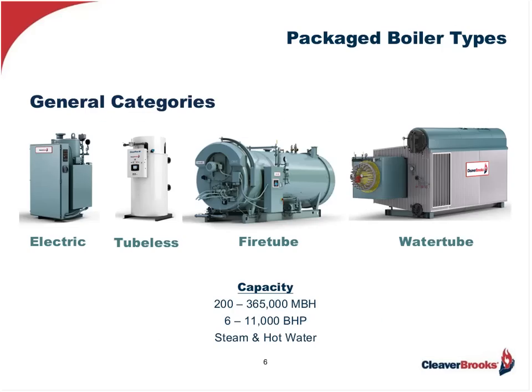The general types of boilers we will be considering today represent the general categories into which all boilers fall. They include the fire tube boiler, the water tube, the tubeless boiler, and the electric boiler. These non-residential boilers span a wide range of sizes, from about 200,000 to 365 million BTU — a horsepower input range from about 6 boiler horsepower to almost 11,000 horsepower — and can be applied to a vast array of applications.